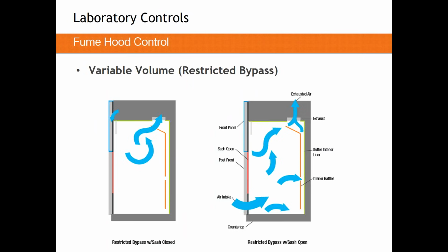On a variable volume fume hood, we can drive down on some of these hoods all the way down to 85 CFM. So on a 4-foot wide fume hood, according to ANSI Z9.5, so long as containment is being maintained, we can get down to 80 or even 85 CFM on these devices, which is much, much lower than the 400, 500, or even 600 CFM they'll need in the open position. So VAV fume hoods are a really simple way to increase your energy savings sometimes.